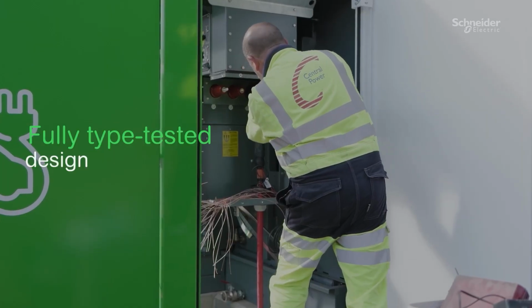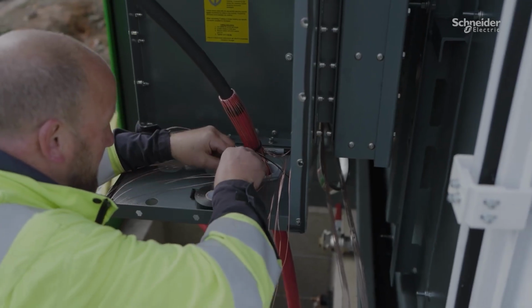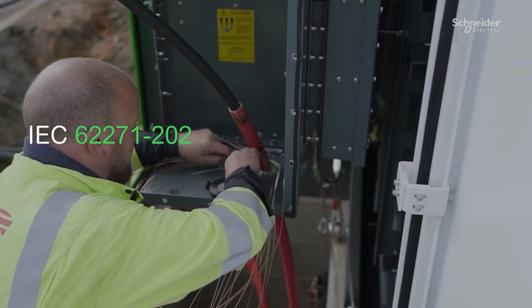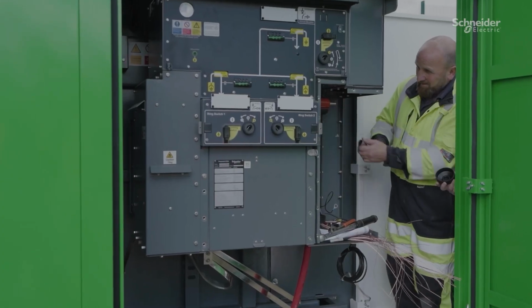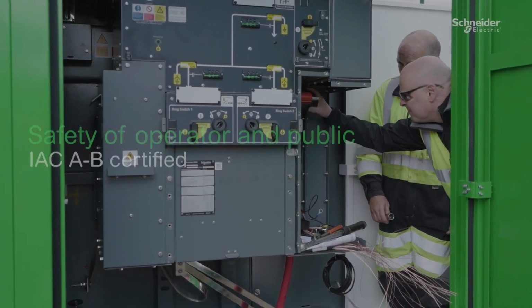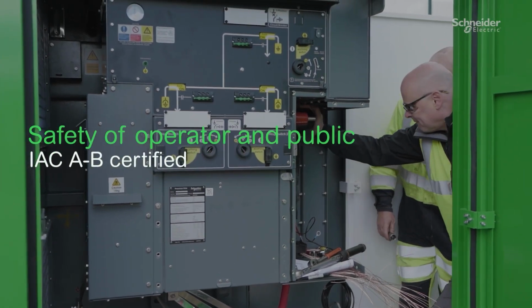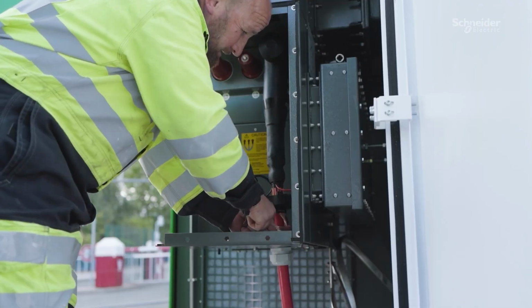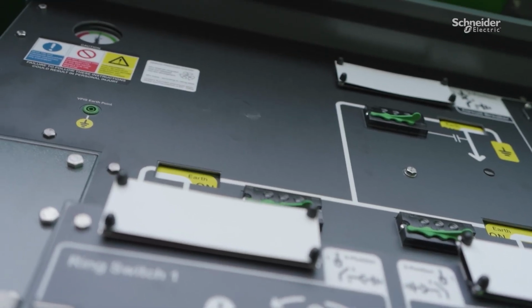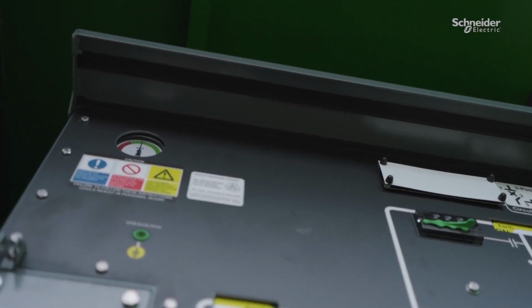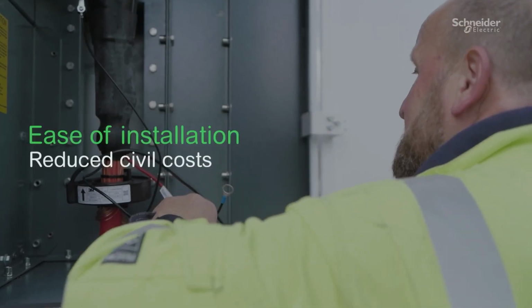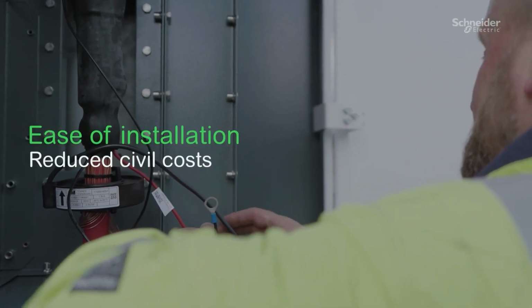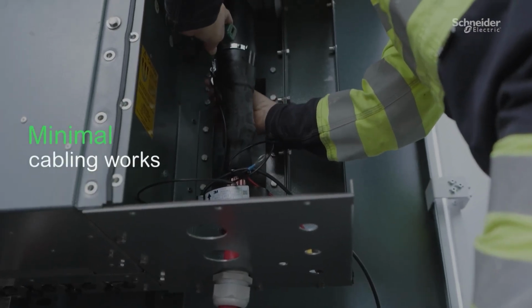MDS features a fully type-tested design, compliant to the latest IEC standards for prefabricated substations, ensuring safety of both operator and the general public. Its compact design incorporates the high-voltage transformer and the low-voltage distribution switchgear into a single unit, ensuring ease of installation, with reduced civil costs and minimal cabling works during commissioning.